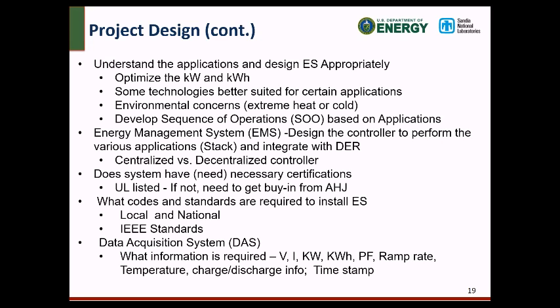The next part is the energy management system, also known as a site controller. This is the control that sits on top of the energy storage system that gives it the command to put out power or absorb power. It's running the application you have decided on, and you might even have stacked applications—doing frequency regulation for a couple hours, then switching over to an arbitrage type application.